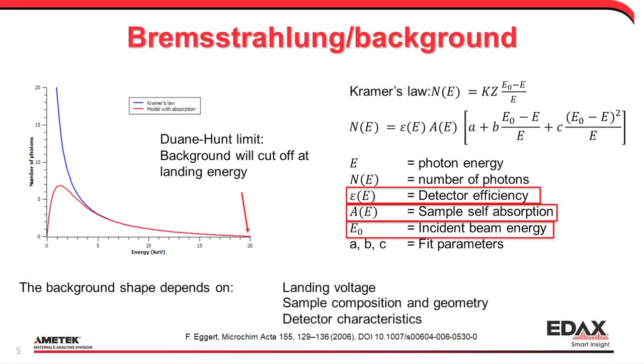We have the reference at the bottom — Frank Eggert is our main theory person. The point of the model we use is that we incorporate the sample self-absorption. Most of the low energy x-rays generated in the sample will never make it out because they are reabsorbed, and we scale by the detector efficiency as well. When we do that, we see a red curve overlaid on Kramers' law that is much closer to what you actually see in the spectrum.